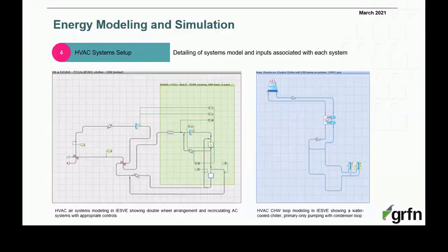For the cooling system, we are using a magnetic bearing water-cooled chiller with variable frequency drives on all the components: chillers, pumps, whether it's the condenser or distribution pumps, and the cooling tower. We got the loads from IES, but we have used our own developed software, which is basically a very complex Excel sheet that will come up with the consumption of every component on an hourly basis for the chiller plant, based on the load profile and the outdoor air conditions.